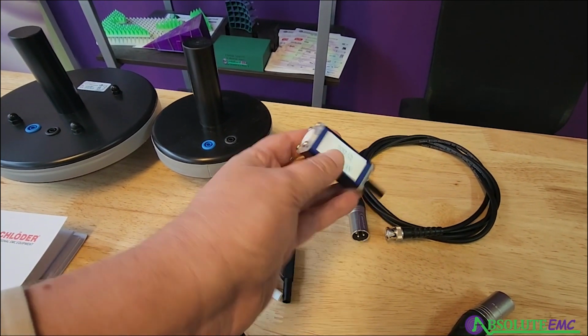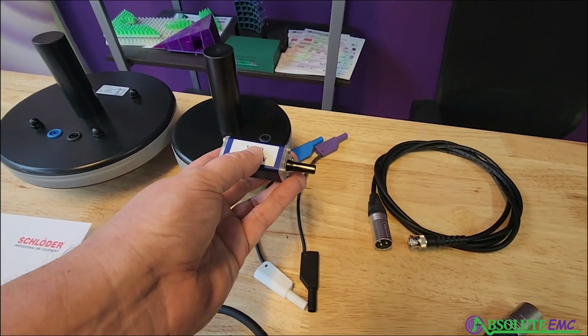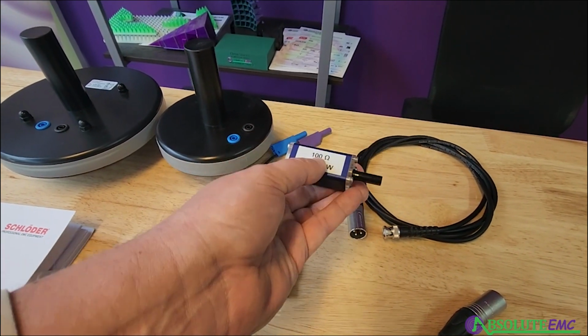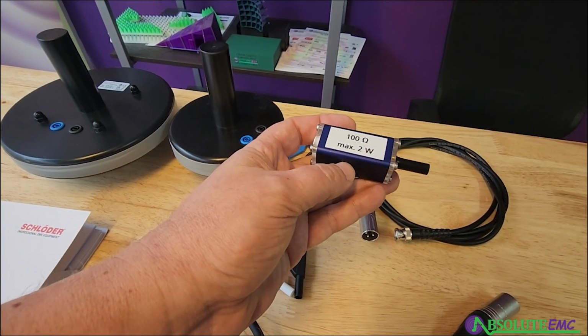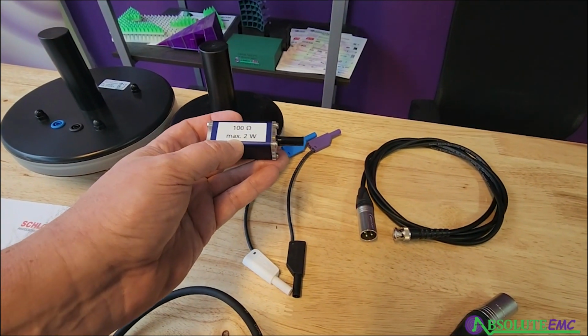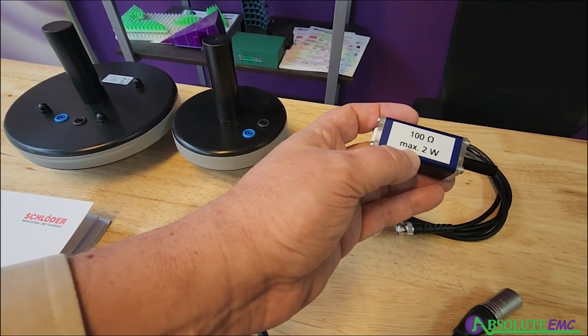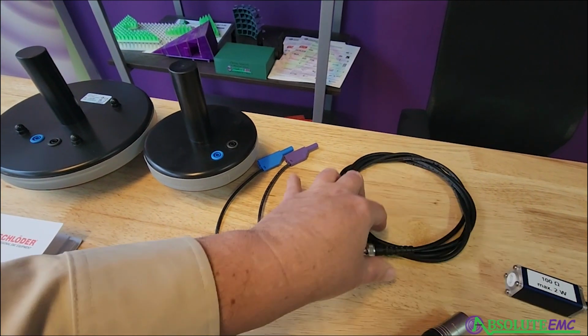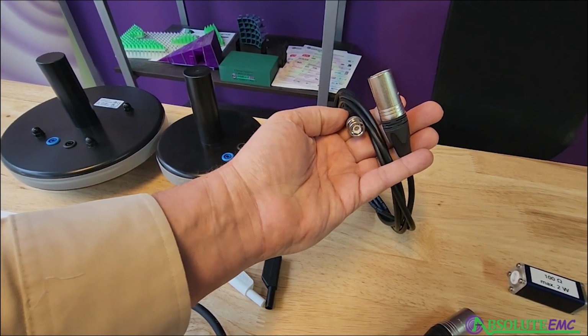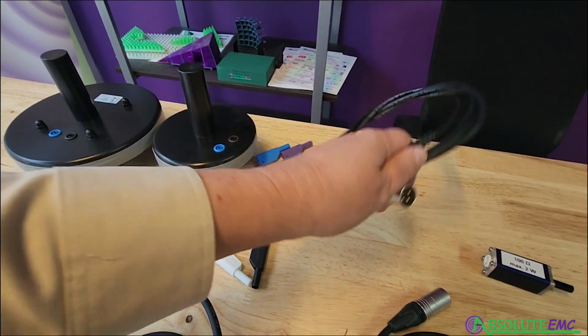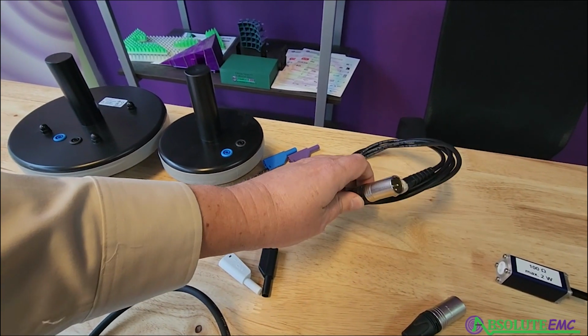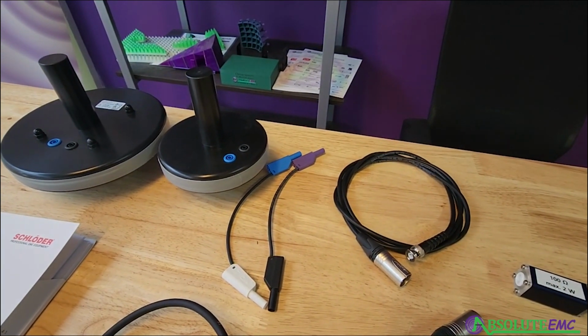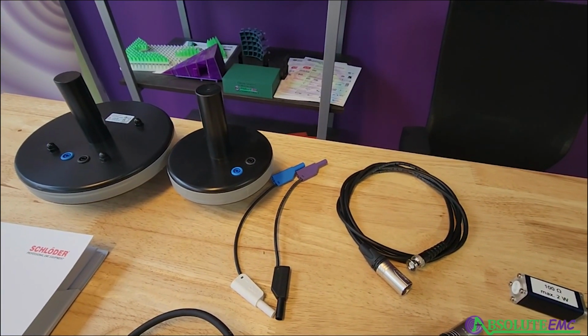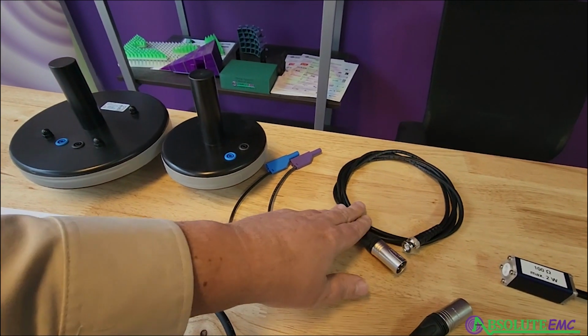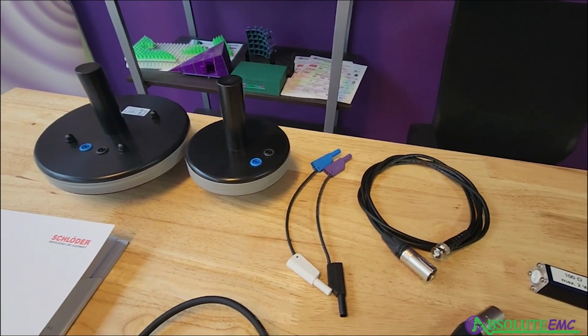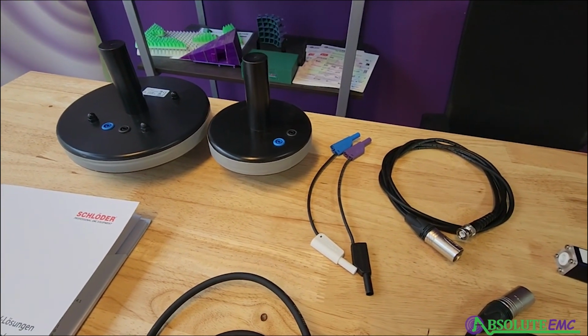There's a 100 ohm impedance which adds to the radiating coil to allow for lower level testing. There's some standards that have some low level magnetic tests that in order to reach those levels, we have to put some more impedance in there and to help with the measurement system inside the generator. There's a cable to connect to a BNC measurement. If you had a different loop sensor, you could use this for that. Or if you had a current probe for measuring conducted emissions, it would connect with that cable. And some patching cables to be used as well if needed.